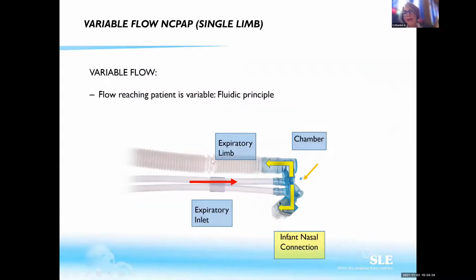It means that if I take my interface here, which is a generator, I will push a flow to make sure that I have the CPAP that I want. For example, still my 5 millibar, I might be around 8 liters per minute here. But what will happen is you will have 50% of the flow going to the patient and 50% going to the expiratory limb, because the pressure here is exactly the same as this one. That's why my flow is equivalent.